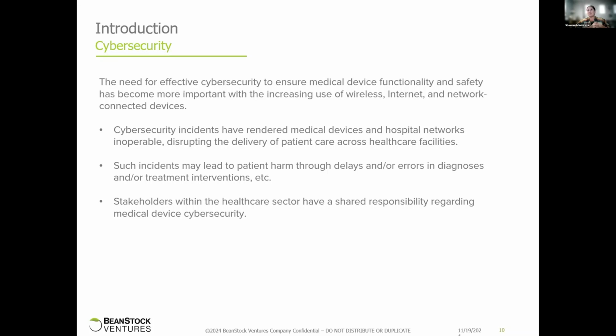The reason is because it's new. When it's new, no one really understands it. They don't understand the risk associated with your product because they haven't seen enough permutations of where the cyber could actually be relevant in a device or not. And so they're just following everything. Here's top to bottom, 12 requirements that need to be done to satisfy cyber. Penetration testing is going to be expected. Threat modeling, which is looking at all the potential threat vectors to determine if there's potential vulnerability, analyzing those, and putting controls in place. FDA has a very well-defined guidance document, and it's actually more technical than most guidance documents. I was quite surprised to see it. It is very specific. Encryption, modern encryption methods are expected. There's really a high bar there.